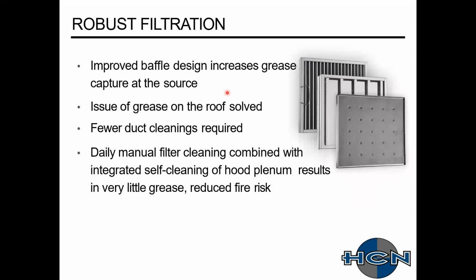Big problems with the duct is a lot of times if those aren't being cleaned normally or on a proper maintenance level, you have fire issues. If you're talking about, let's say, a solid fuel application, creosote kind of starts to build up on those, and it has a lower flash point than your typical grease does itself. I think creosote's flash point's like 130 degrees, where grease is a little bit higher. I think it's like 2 something. So the more that we can clean these or capture that grease at those hoods, the better it is for your fire suppression as well.